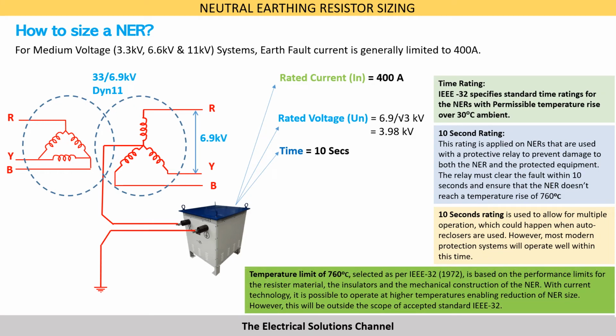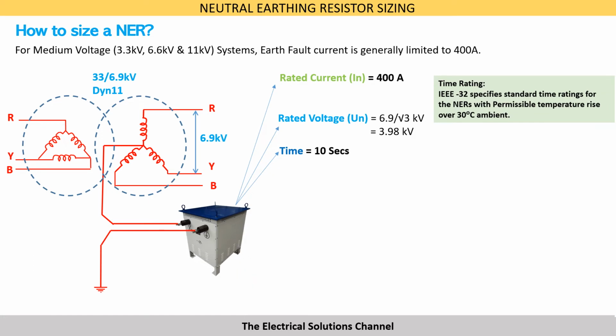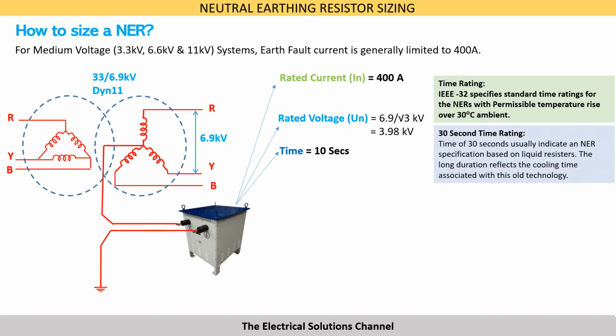The temperature limit of 760 degrees C, selected as per IEEE 32/1972, is based on the performance limits for the resistor material, the insulators, and the mechanical construction of the NER that was prevalent in 1972. With the current technology, it is possible to operate at higher temperatures, enabling reduction of NER size. However, this will be outside the scope of the accepted standard IEEE 32. The 30-second time rating usually indicates an NER specification based on liquid resistors. The long duration reflects the cooling time associated with this old technology.